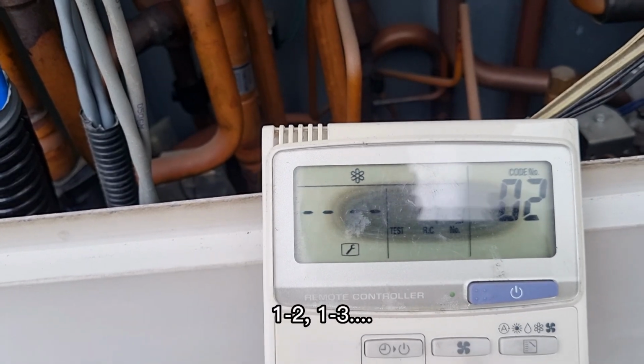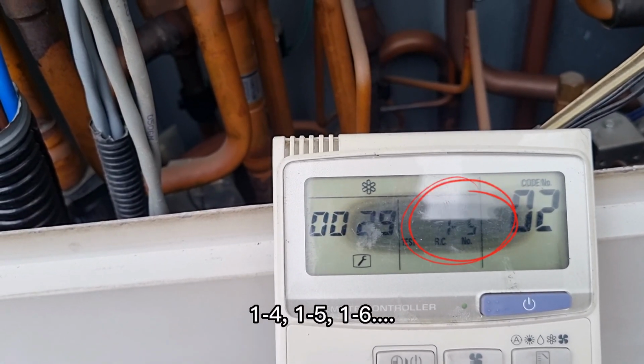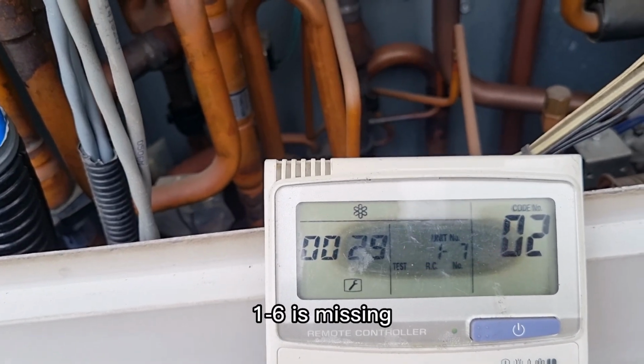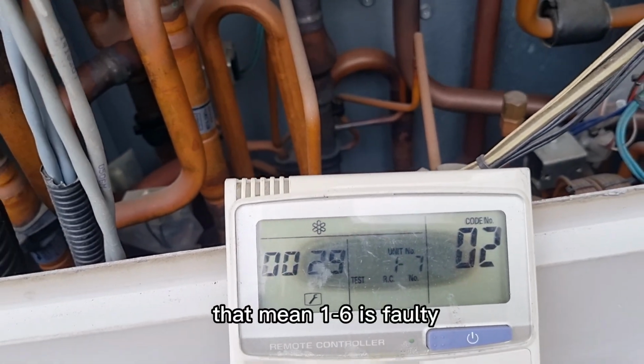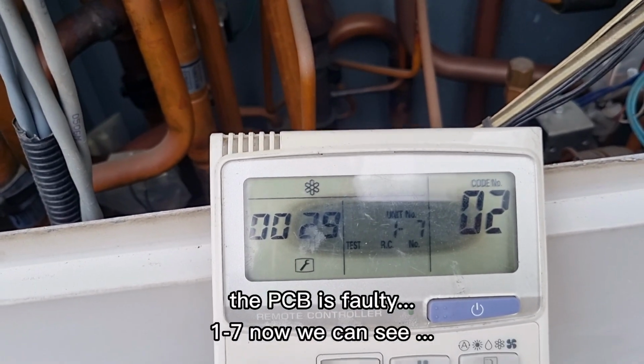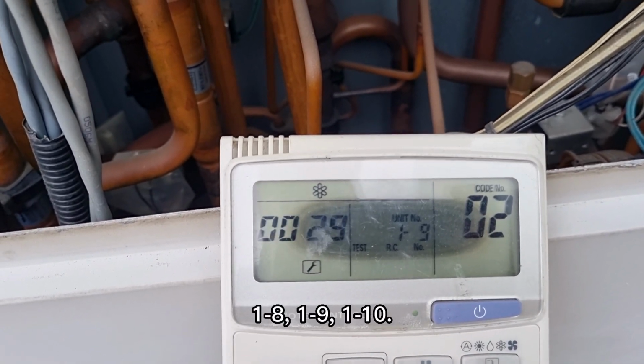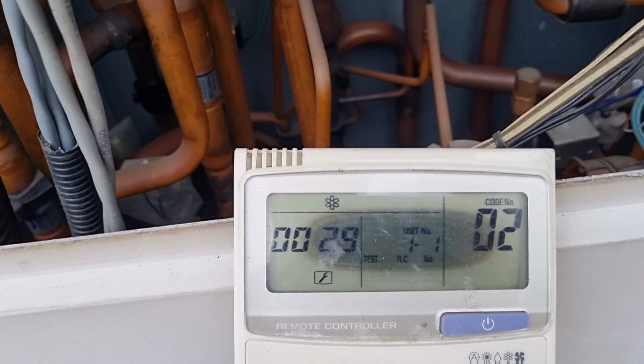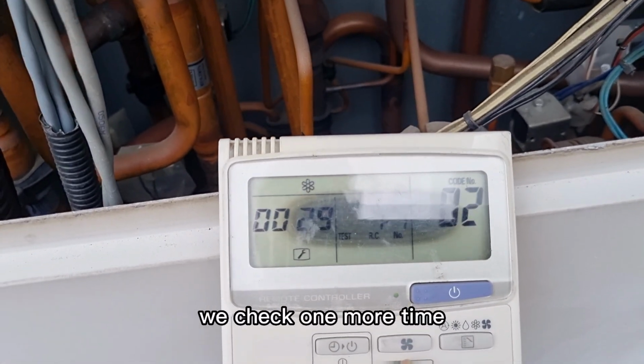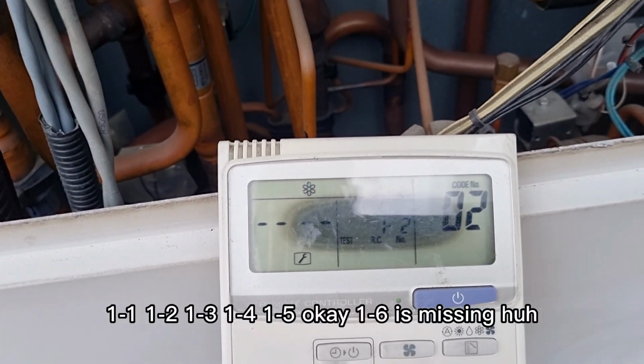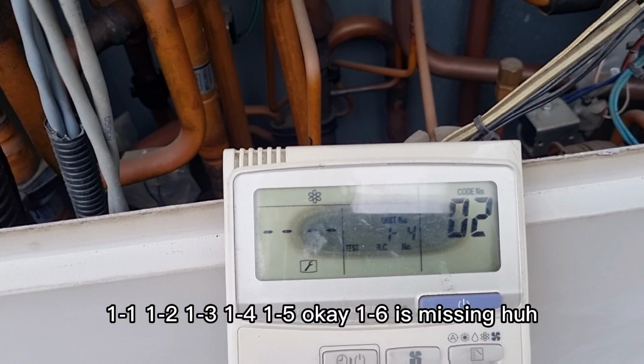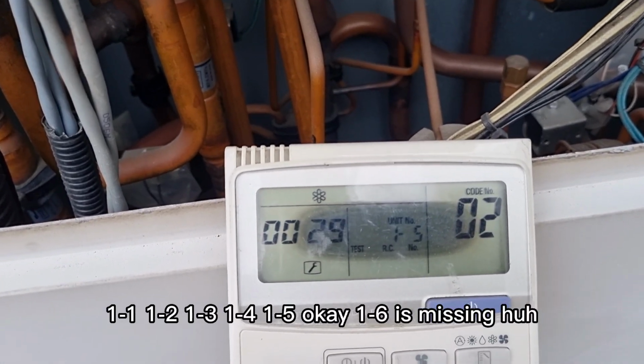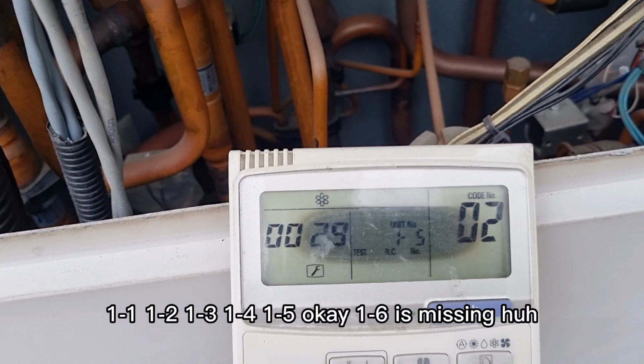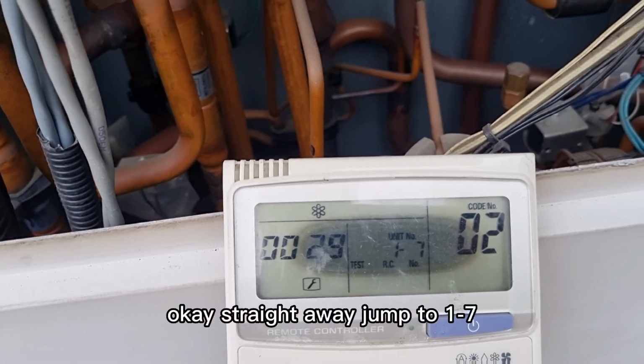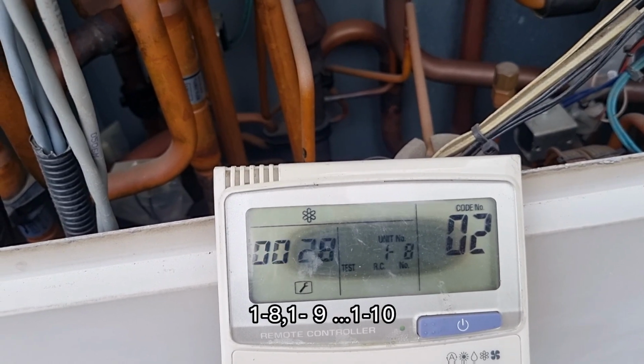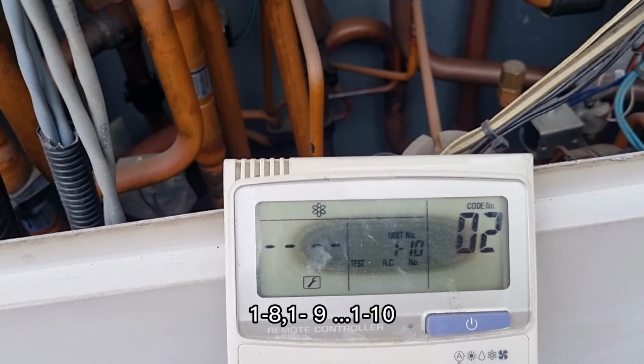1-2, 1-3, 1-4, 1-5, 1-6. 1-6 is missing. That means 1-6 is faulty. 1-7 now we can see. 1-8, 1-9, 1-10, 1-1. Okay, we check one more time. 1-1, 1-2, 1-3, 1-4, 1-5. Okay, 1-6 is missing. Okay, straight away jump to 1-7, 1-8, 1-9, 1-10.